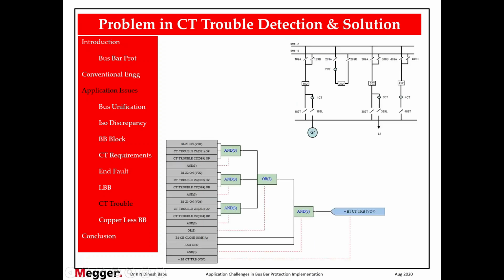The last one is a 3-bus arrangement, 2 main bus and 1 transfer bus. So whether the bay is in zone 1, check for the trouble condition. Zone 2, check for the trouble condition. Zone 3, check for the trouble condition. When all are satisfied, check the breaker is closed, undercurrent is picked, then CT trouble in that particular zone.